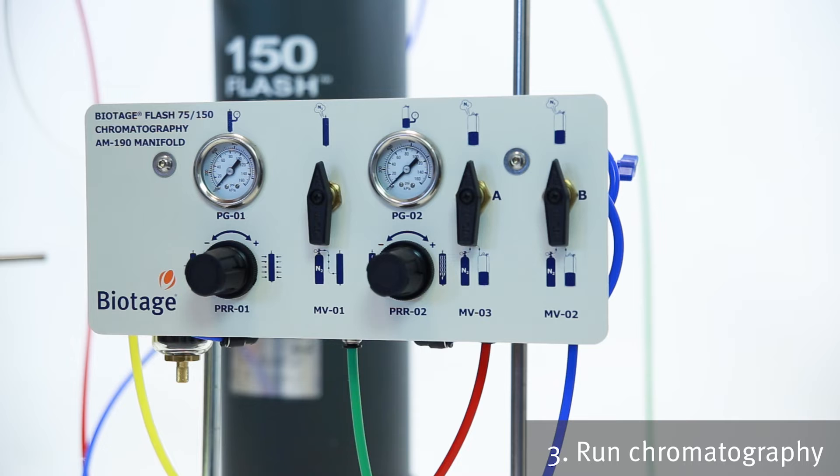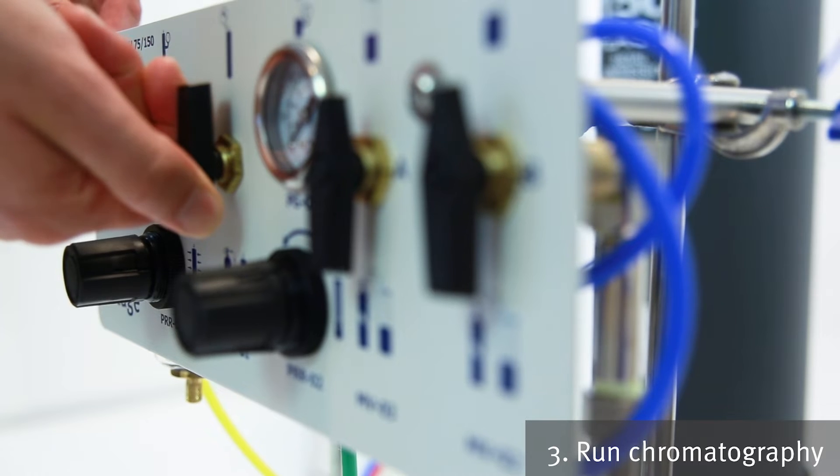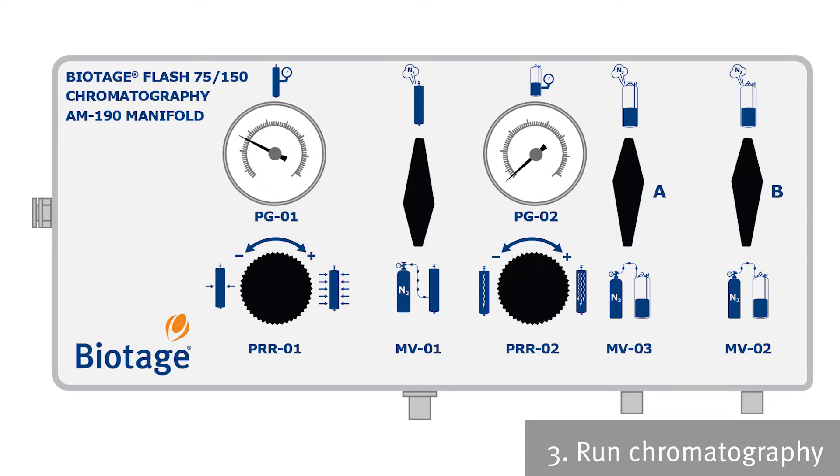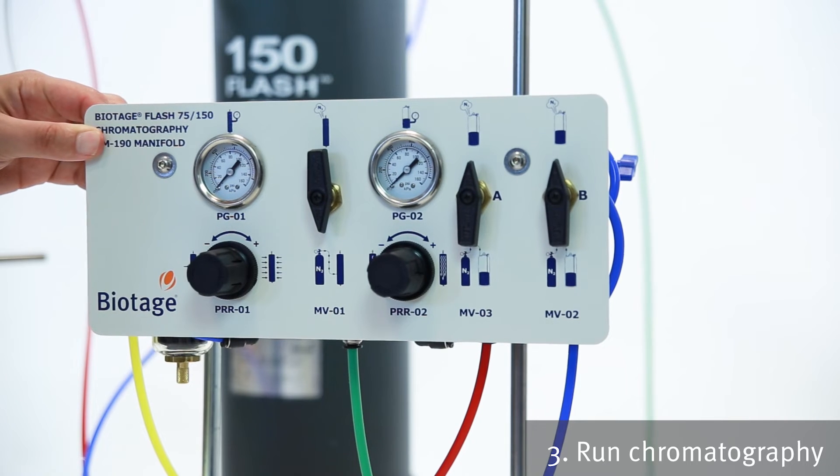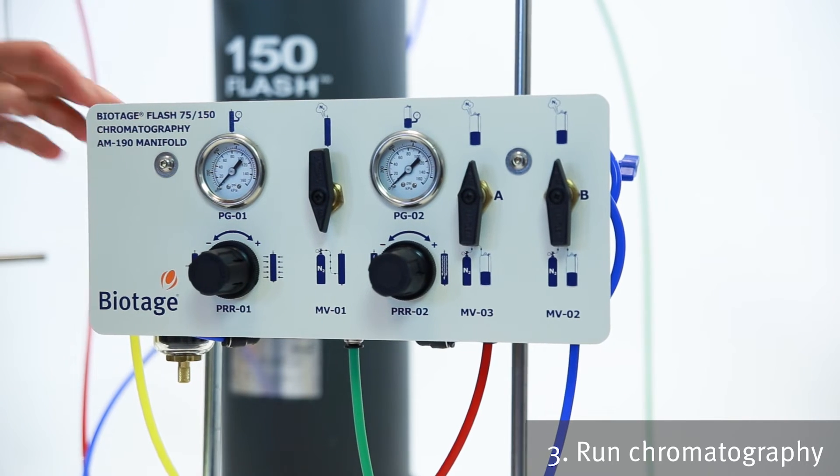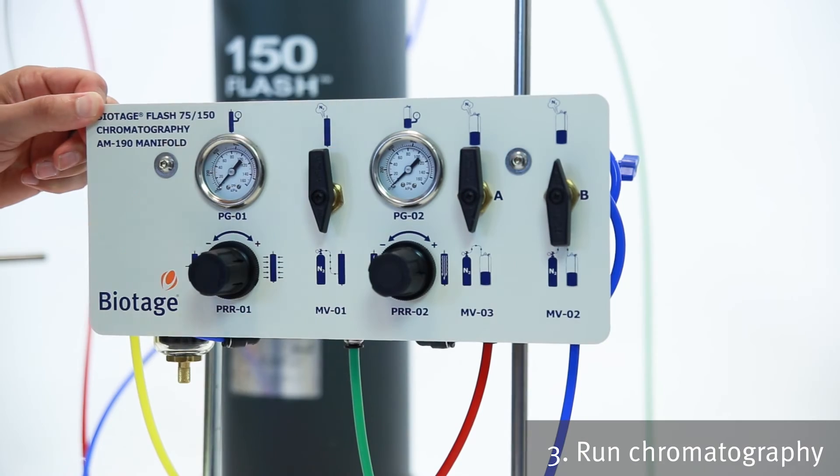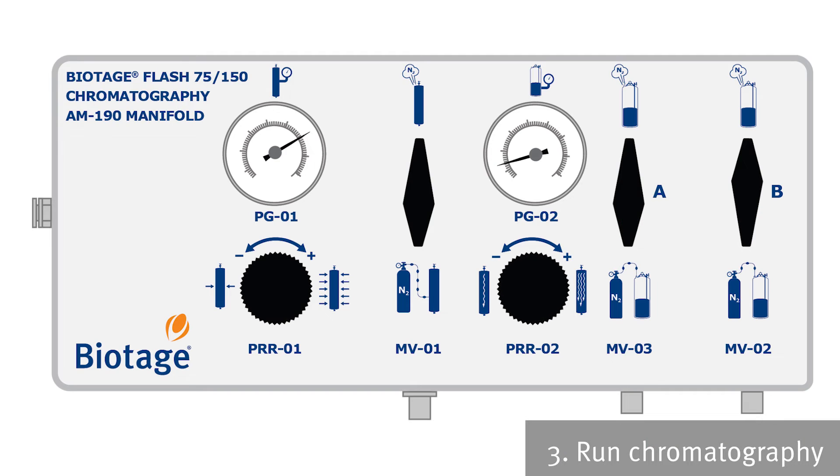So first up, we've got to make sure that the pressure is 100 to 120 psi. And then we're going to make MV-01 live. And then set the pressure that we want to run the system at. This is going to set the pressure for the radial compression module. Next up, we're going to pressurize our solvent tank. We're on solvent position A. So we're going to go live on MV-03. Set the pressure to the tank. We're good to go.